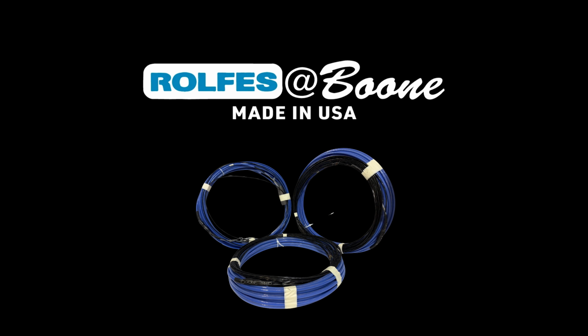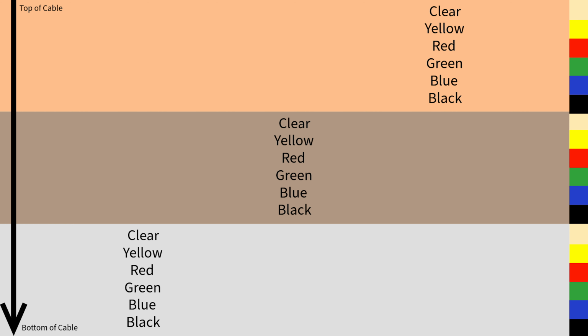Before we begin testing your cable, there are a few things you should understand. First, a thermocouple is created by soldering a silver constantan wire to a copper wire. Our temperature cables have 6 copper wires per 1 silver constantan wire. Next, each temperature cable has a color pattern. We can use this color pattern to locate where a thermocouple is on each cable. For a Rolfes at Boone temperature cable, we use this color pattern.